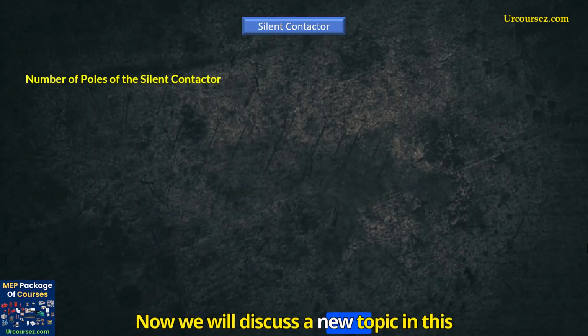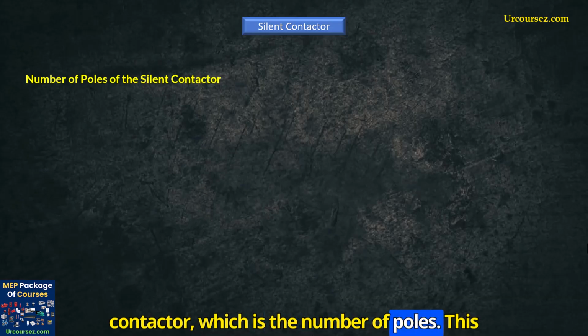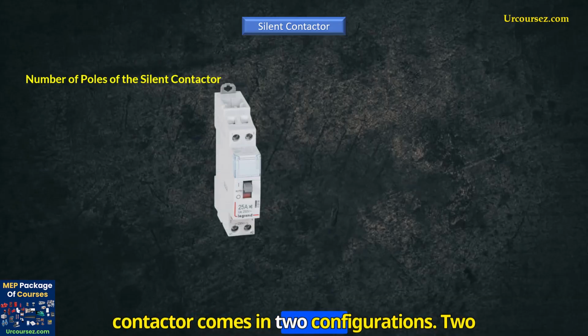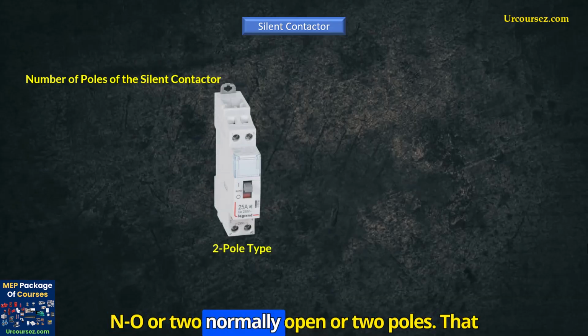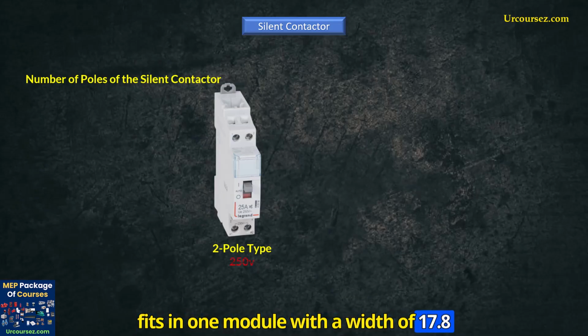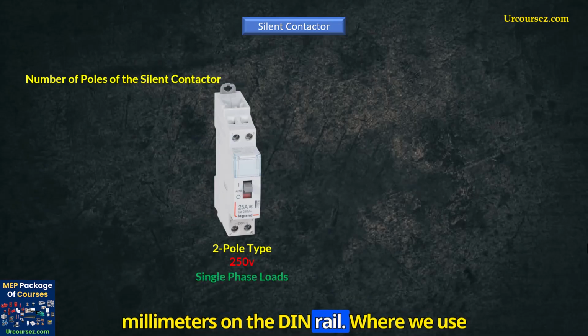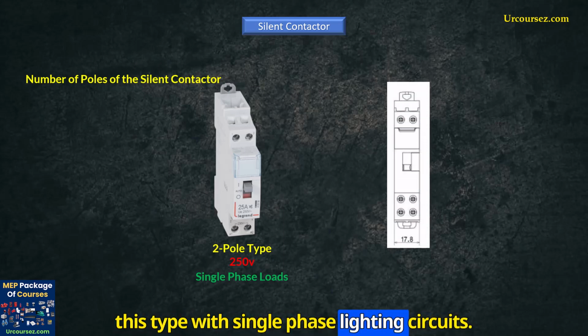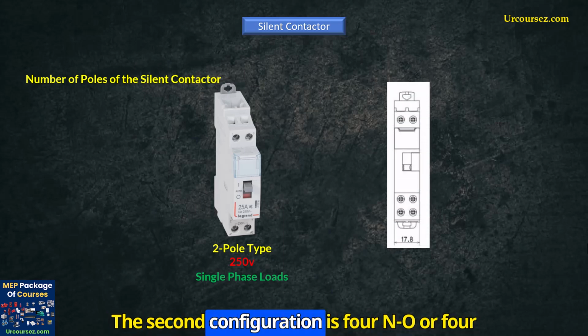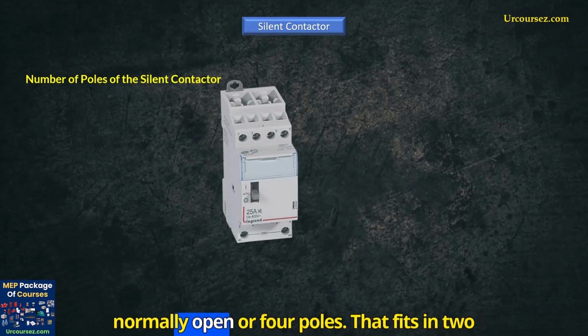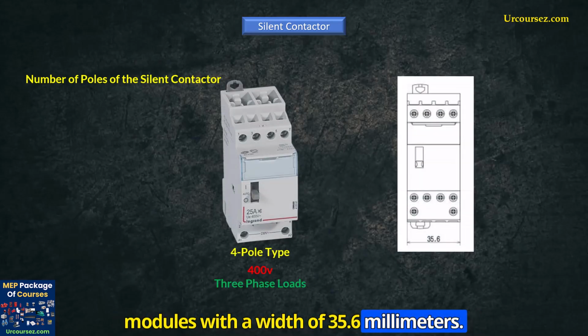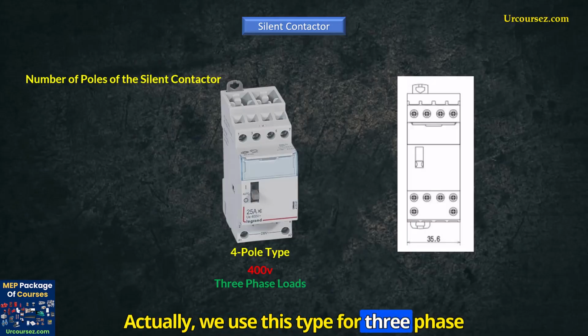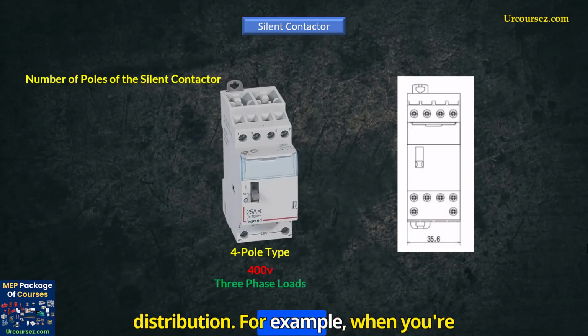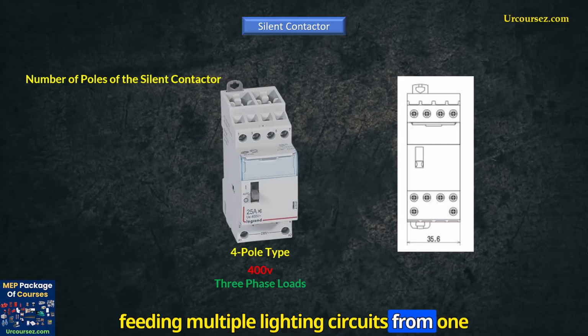Now we will discuss a new topic in this contactor, which is the number of poles. This contactor comes in two configurations: 2NO, or 2 normally open poles, that fits in one module with a width of 17.8 millimeters on the DIN rail, where we use this type with single-phase lighting circuits. The second configuration is 4NO, or 4 normally open poles, that fits in 2 modules with a width of 35.6 millimeters. We use this type for 3-phase distribution, for example, when you're feeding multiple lighting circuits from one contactor.